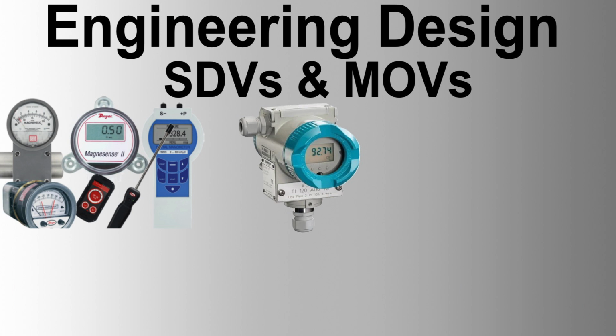Accessories. Shutdown boxes. Local controls and accessories shall be mounted in a shutdown box. Shutdown boxes shall be fully enclosed, 316 SS enclosures separate from the valve, containing all control and shutdown solenoids, manual valves, and other controls as detailed in the datasheets and control schematics.